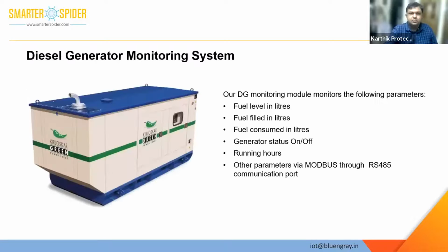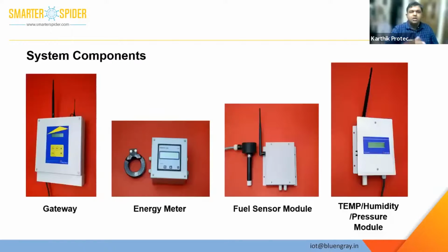to understand how the pump is running. Coming to the next thing, a DG monitoring system, where we monitor the fuel level in liters, fuel filled in liters, fuel consumed in liters, on-off status and runtime. If it has an RS485 communication port, we integrate with it through Modbus. Coming to the system components: this is the gateway, which acts as a communication bridge between the different wireless modules and the cloud.